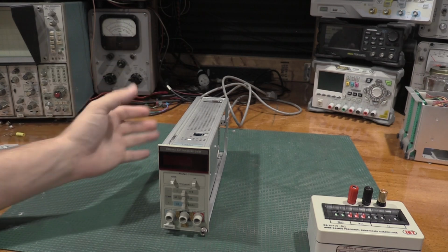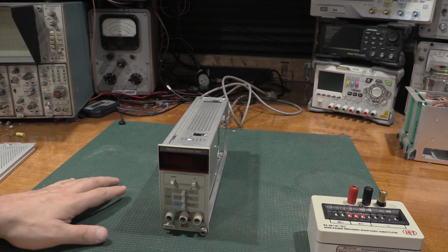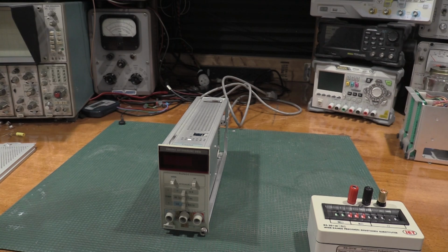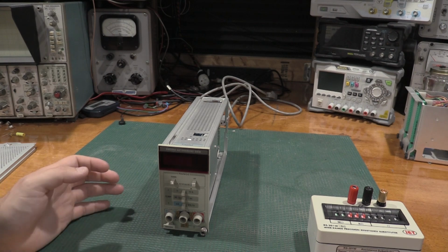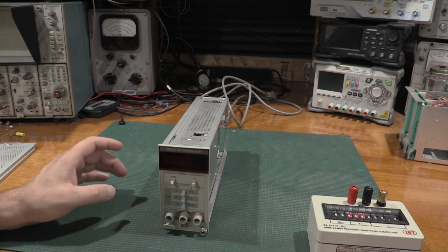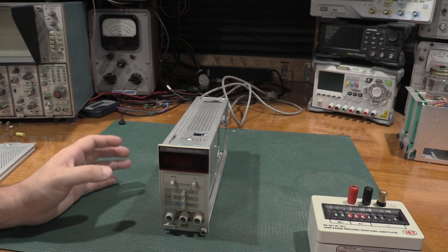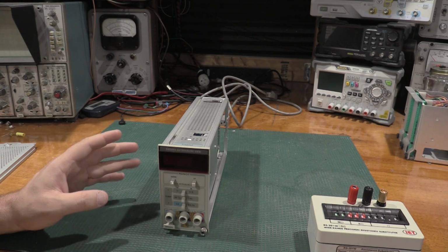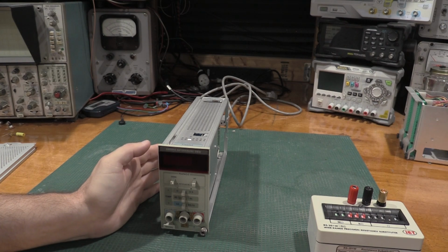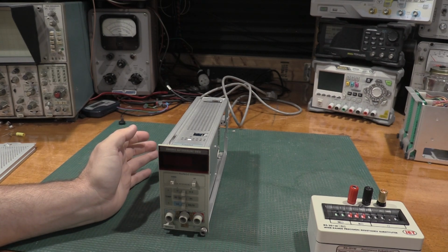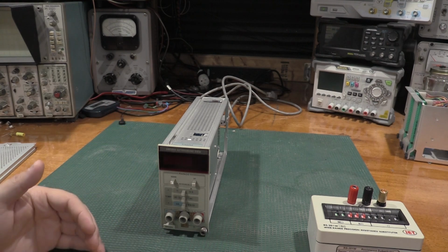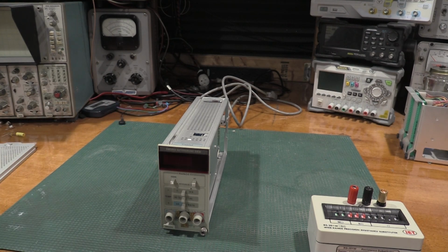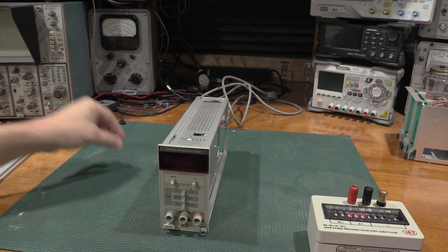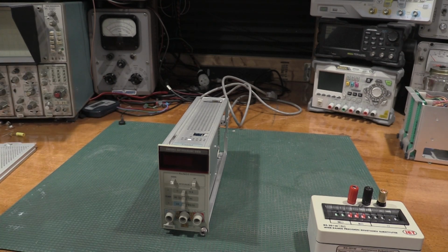But this is where we're shifting from adjustment into calibration. And you can tell this by the calibration documentation. On the older stuff, you'll have adjustment points, adjust to this, and every time you send it out, it got tuned up a little bit. When we shift to verification versus alignment, you start getting tables with limits in the service documentation. So you'll have low limit, high limit, what it was actually measured. And that's it. That's a calibration. As long as it's within those two, it's in spec, everything's good to go.